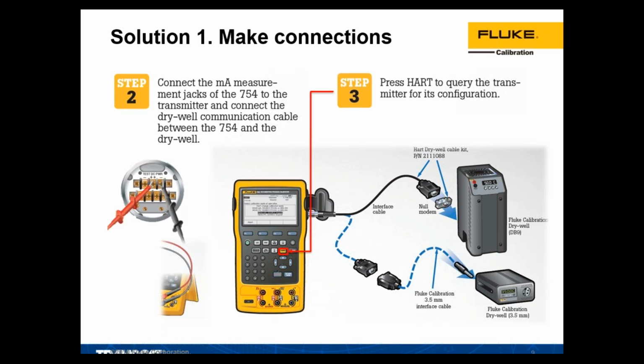We do need to connect the 754 to the transmitter. I just got a little illustration of the connections there on the left. But then on the right here, we need to hook up a special cable to connect to the dry well. So it's called the HART dry well cable. That's the model number, and then for your convenience, I've got the part number, the Fluke item number, also listed right there as 2111088. What it consists of is an RS-232 cable with a LEMO connector on one side, and then it's got a special null modem connector on the other side to make sure that all the connections line up correctly when you connect it to the serial port on the dry block.